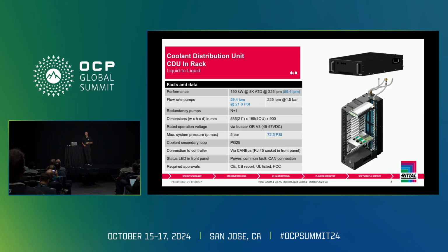So a little bit of deep dive on some of the components. We have some of these components on show at our booth, both here and on the outside on the entrance. But this is an In Rack CDU, just some facts and figures around it. All within a 4OU footprint, we can develop something like 150 kilowatts at an 8 Kelvin approach temperature. All N+1, so within that single unit, the In Rack solution, we have 3 pumps. One is typically idling, whilst 2 are running. So 150 kilowatts, N+1 redundancy. As you'd expect, PG25 as a liquid interface, and all the required approvals that we need, CE, UL compliant across the world, UL listed, etc., etc.